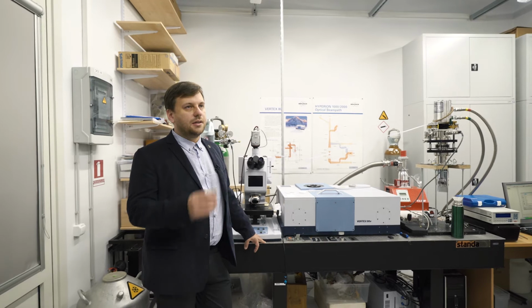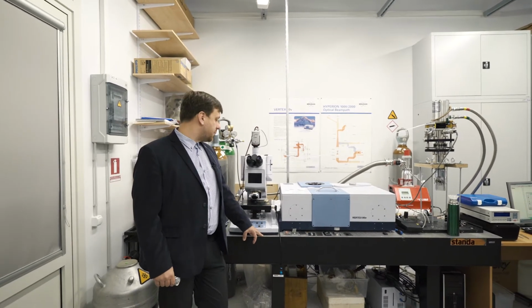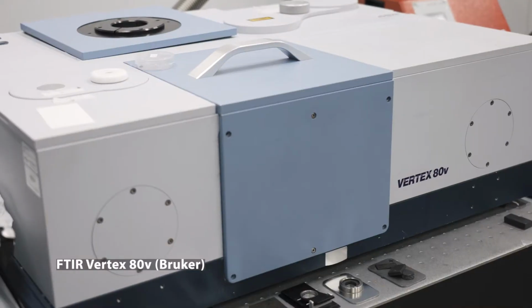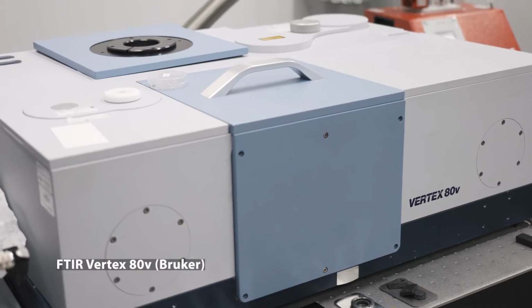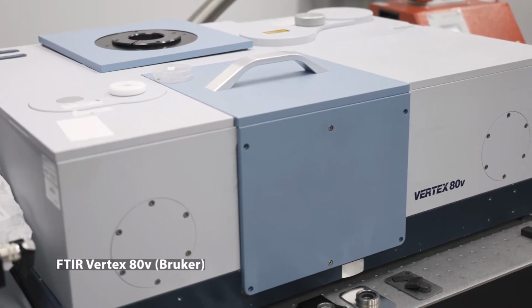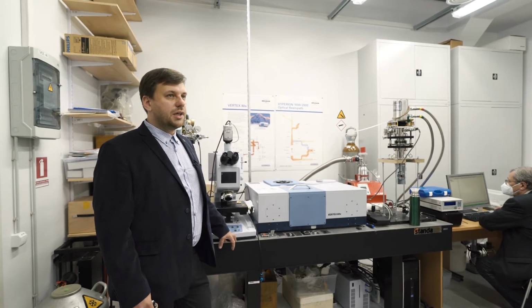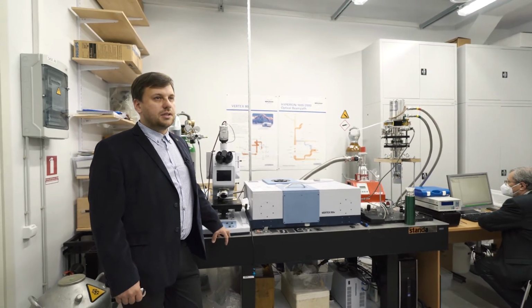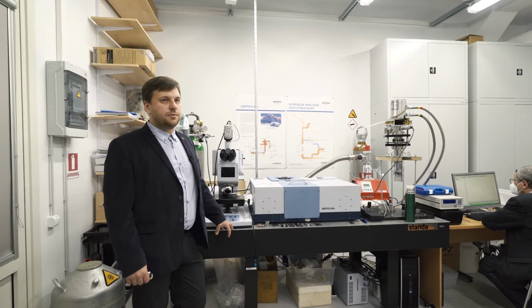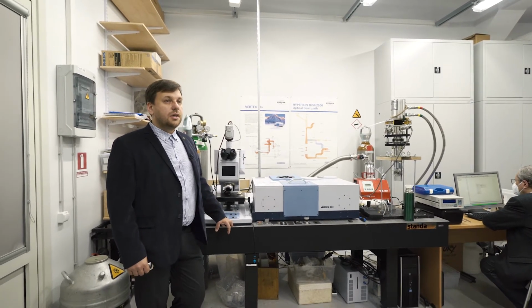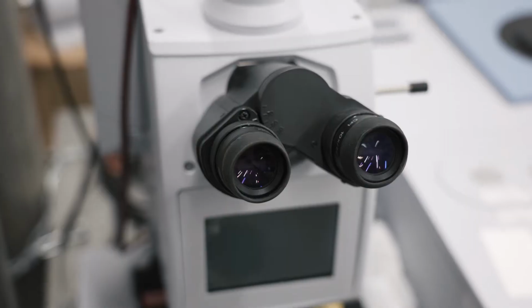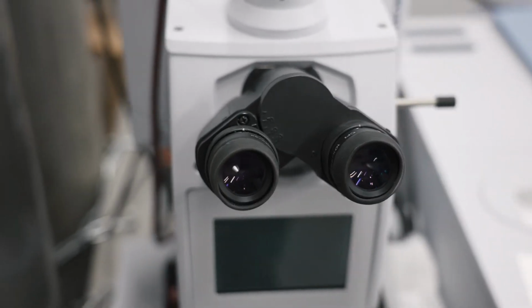This is the Laboratory of Vibration Spectroscopy, and we have a Fourier transformation infrared spectrometer here from Bruker, which is one of the most powerful benchtop vacuum spectrometers available. Its spectral range is from 10,000 reciprocal centimeters down to 10 reciprocal centimeters. Currently it is in the process of upgrade to include a bolometer, thus extending the measurement limits and sensitivity further in the terahertz region. It is also equipped with a microscope, allowing for measurements on microscopic scale.